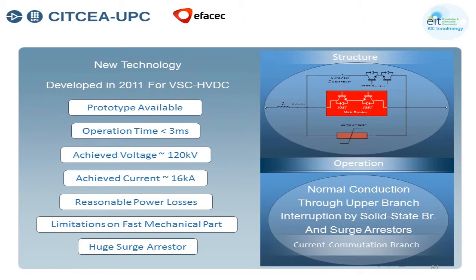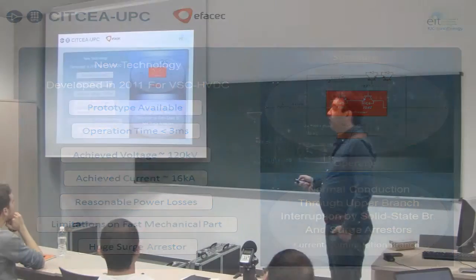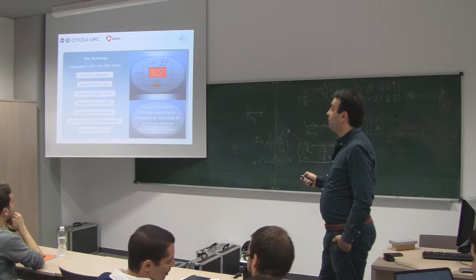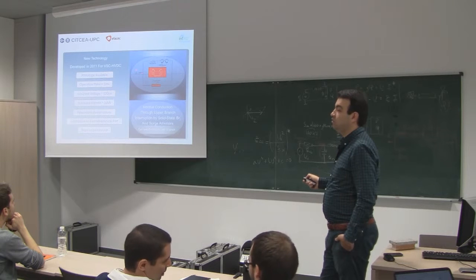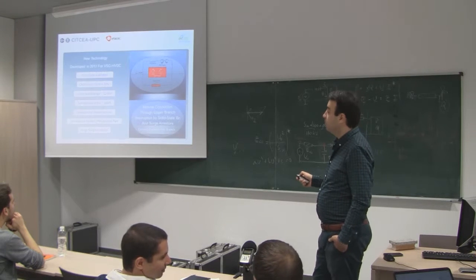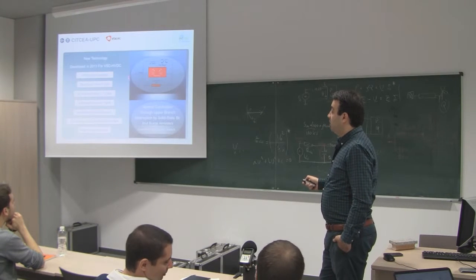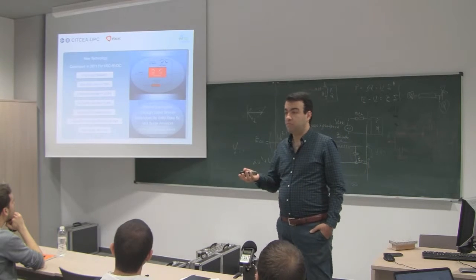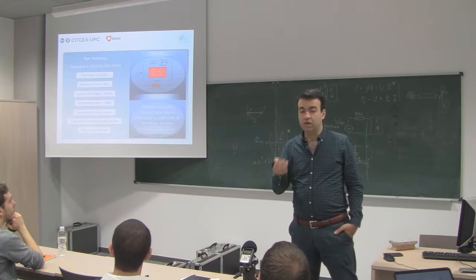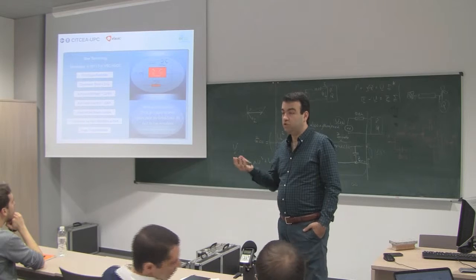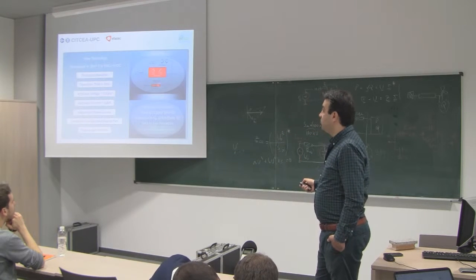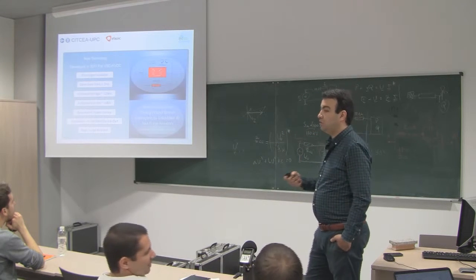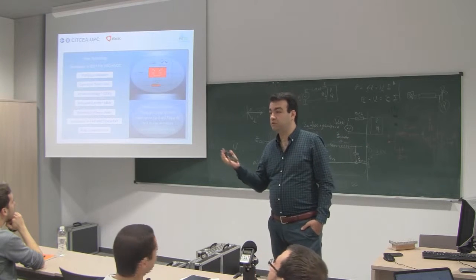So the operation is that in normal operation, you will activate this branch, so the current will flow through the mechanical breaker and these IGBTs. And when you have a fault, you will commutate the current to this branch and you will interrupt by this. And the energy which is released from the inductor of the cables, and also from the interruption, the switching, will be damped inside this surge arrestor, which are usually metal oxide varistors.